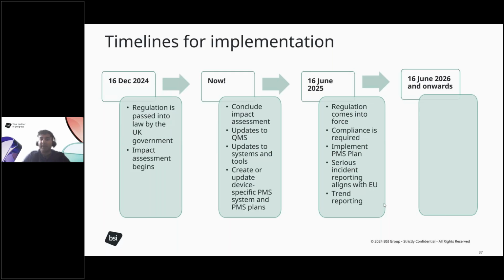Serious incident reporting aligns with the EU in most cases, and there is some trend reporting requirements. There have been some changes in reporting requirements for vigilance and FSCAs as well. So please do make sure you have looked at these. And ongoing things that you need to look after is for all your devices, because this statutory instrument is for all devices placed onto the GB market, you will have to create a PSUR, which is due within 1 year from the 16th of June 2026, and a PMSR, so for the lower risk devices, it is due within 3 years of 16th of June.